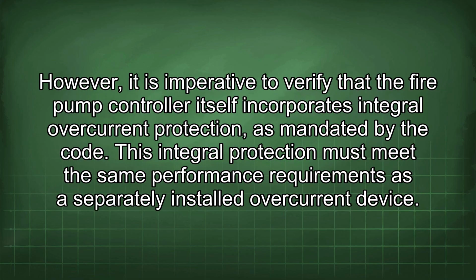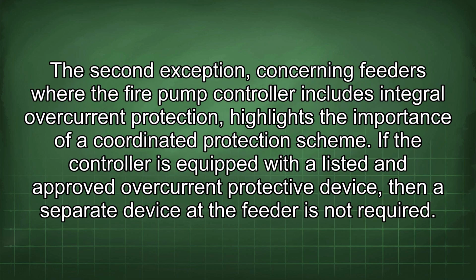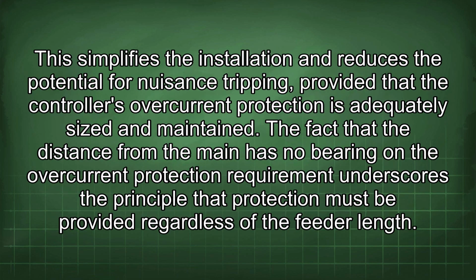However, it is imperative to verify that the fire pump controller itself incorporates integral overcurrent protection as mandated by the code. This integral protection must meet the same performance requirements as a separately installed overcurrent device. The second exception, concerning feeders where the fire pump controller includes integral overcurrent protection, highlights the importance of a coordinated protection scheme. If the controller is equipped with a listed and approved overcurrent protective device, then a separate device at the feeder is not required.